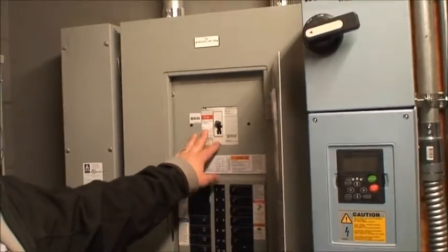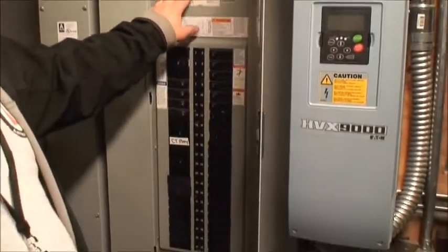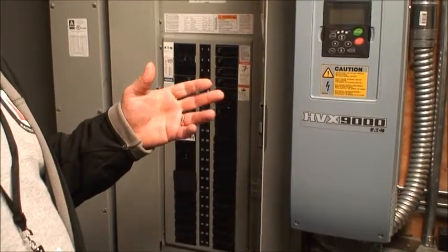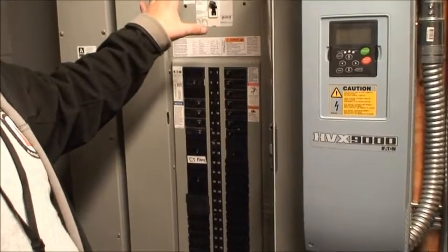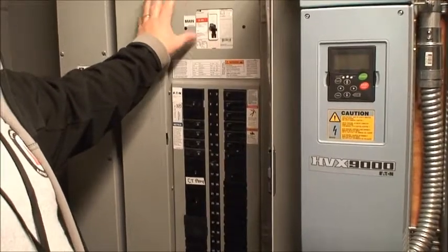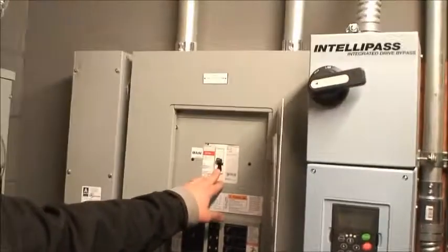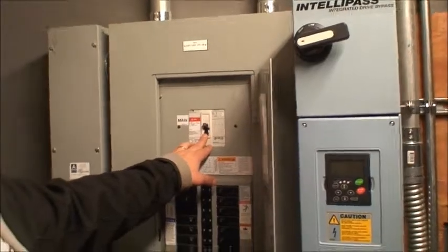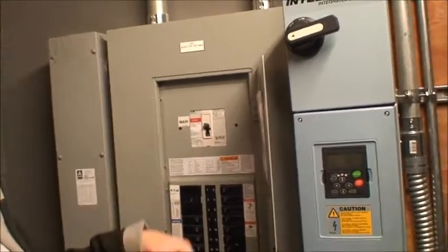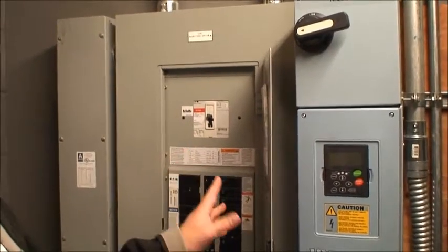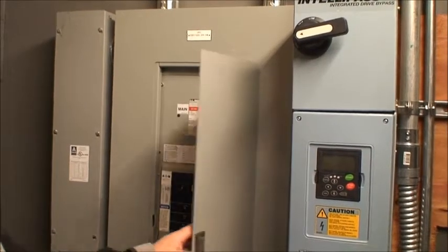Okay. And there's also a breaker downstairs. So it has a breaker here and a breaker downstairs, so if you want to kill it from below, you could kill it from downstairs. Okay. The big thing is to be able to open this panel up. Even if you shut this down, you're still live to the line side of this breaker. Yep. So you want something that will shut off the panel if you ever had to open up this cover. Okay. And that would be done from downstairs.